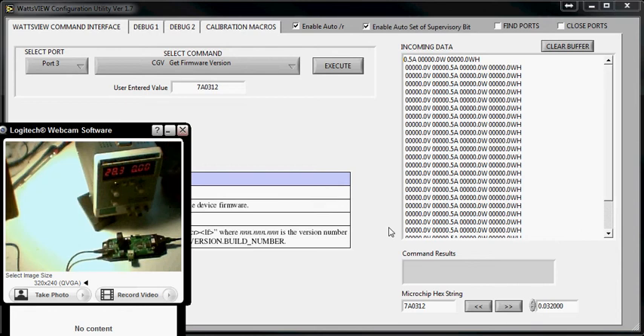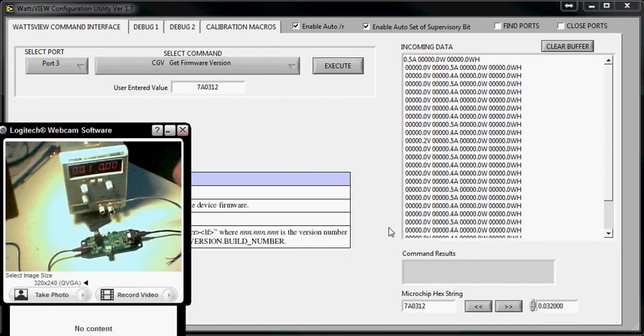The first thing you need to do is connect the WattsVIEW sensor to the power supply. First we'll connect the black wire to the negative terminal and the red wire to the positive terminal. Just a quick word on safety: you never hook up anything with the voltage turned on, and always use wire that's rated for the application that you're doing.